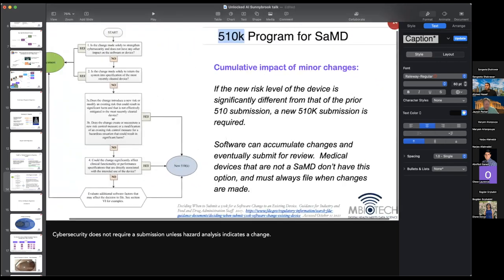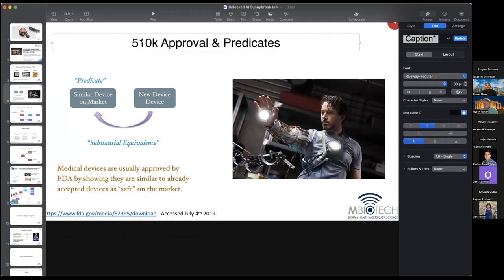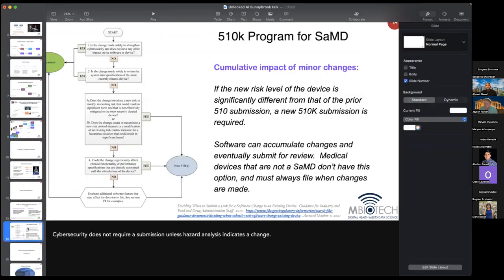The main issue is that companies are given more responsibility and power here. With traditional medical devices, any change you make requires a 510-K or PMA submission. But when we get into software, it's a little different. The manufacturer has been given the discretion and responsibility to decide whether a change is minor or major. If the change is very minor, the manufacturer won't even submit a 510-K. If it's a bigger change, then at the manufacturer's discretion, they can decide to submit a 510-K.